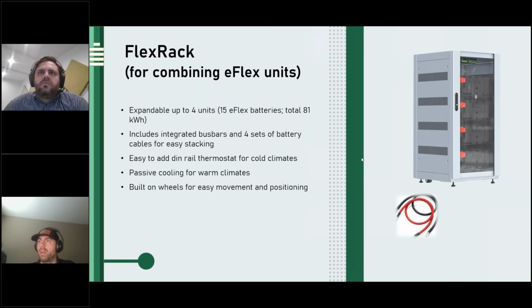Another question: for the 15K, should you not include a double pole, double throw bypass switch as recommended for the 12K between the grid connections? That's correct, you no longer need the bypass switch. If it's a 200 amp service or less, you can land that directly on the inverter without any bypass switch. We can still put the system into bypass mode, so if the grid is available and something goes wrong, we can reconfigure to continue supporting the system up to that 200 amps.